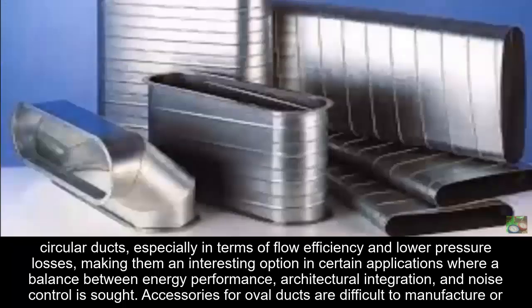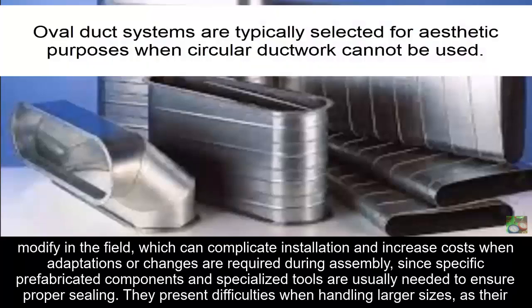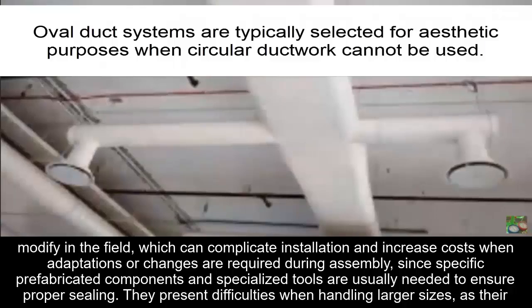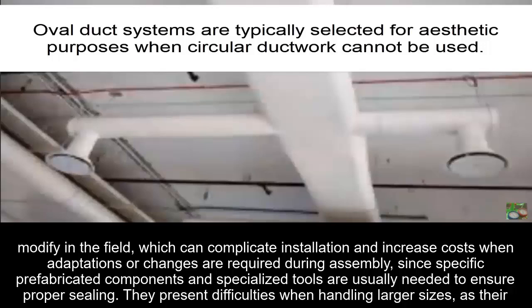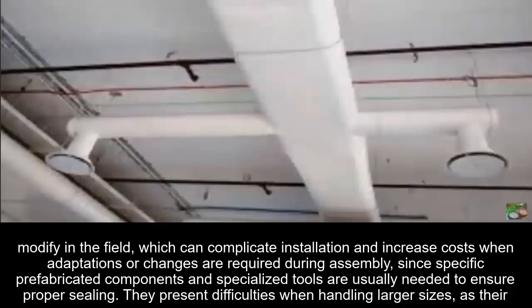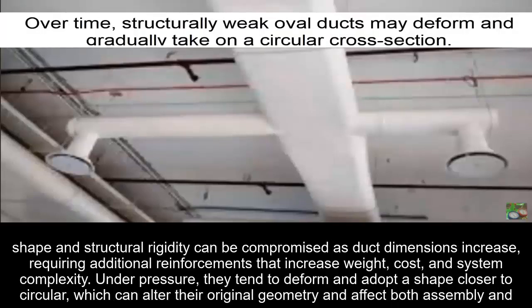Accessories for oval ducts are difficult to manufacture or modify in the field, which can complicate installation and increase costs when adaptations or changes are required during assembly, since specific prefabricated components and specialized tools are usually needed to ensure proper sealing. They present difficulties when handling larger sizes, as their shape and structural rigidity can be compromised as duct dimensions increase, requiring additional reinforcements that increase weight, cost, and system complexity.